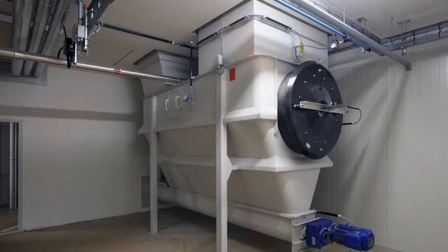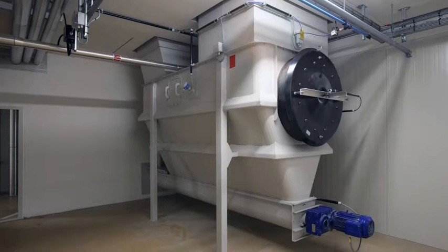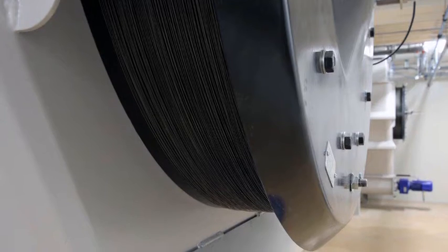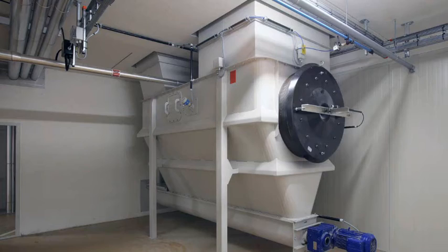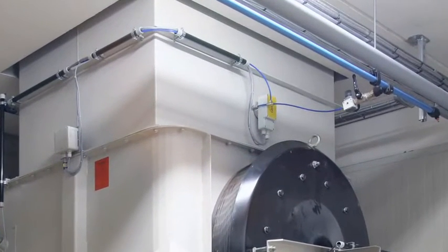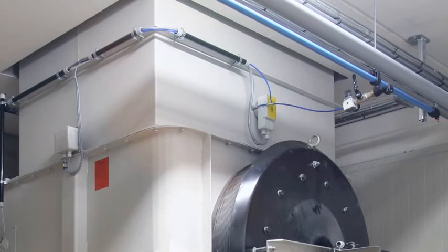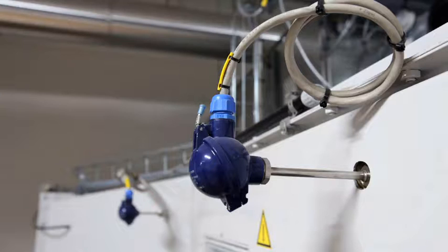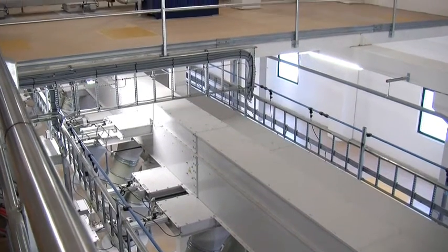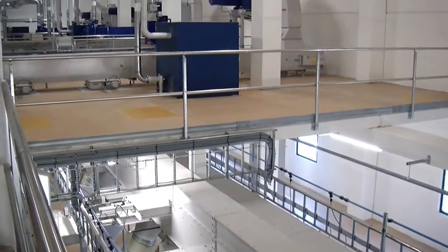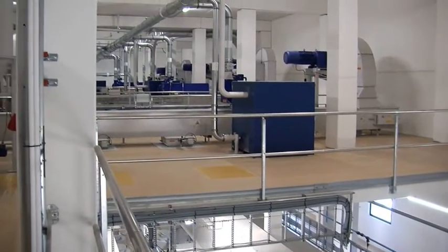Dust and any sparks from the hammers form a potential explosion risk. The bins after the hammer mills are equipped with explosion relief. Moreover, at several locations in the process, sensors have been fitted for spark, temperature and smoke detection. Valves in the circuit close automatically and the machinery is switched off after detection.